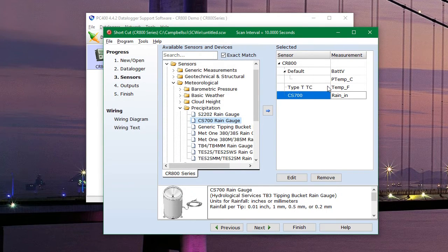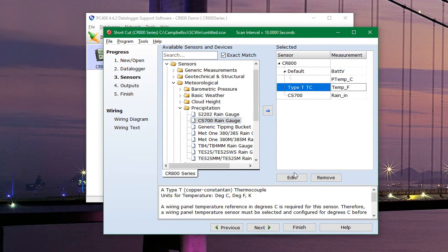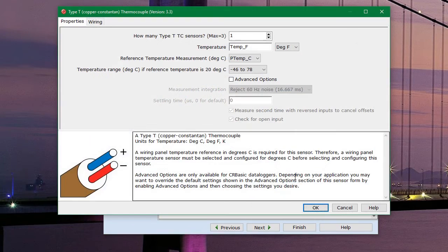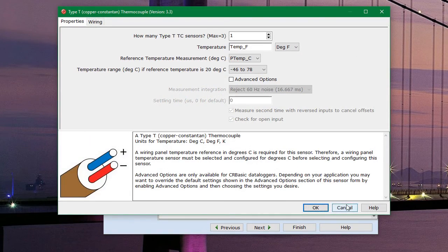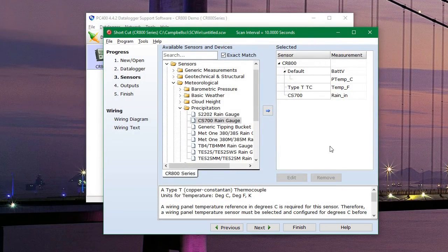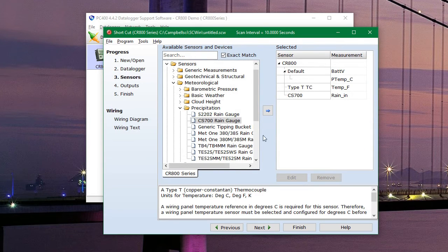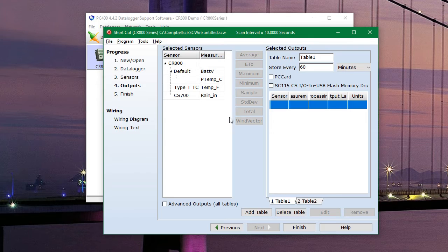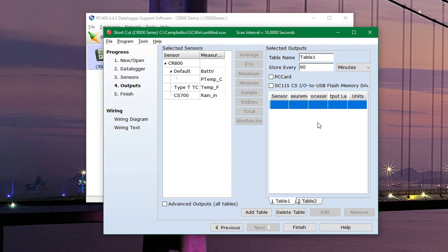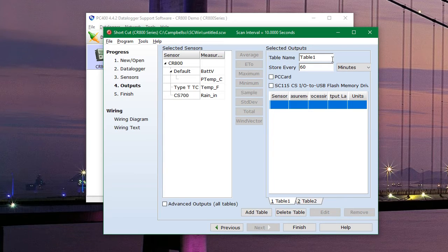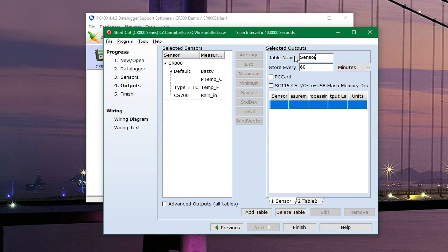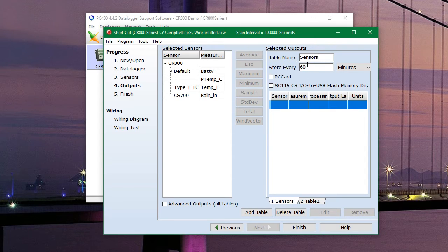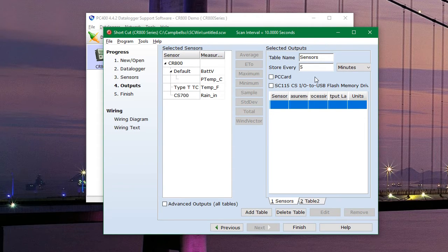And there we have our two sensors. If you need to make any changes to them, you can hit the edit button down here, which will pop that window back up. And so now we can go to the outputs page where we can configure what data will actually be saved to the logger. The data is organized into tables. And so on our first table, we can name it anything we want. We'll call it sensors. And we want the data to be saved every 5 minutes.